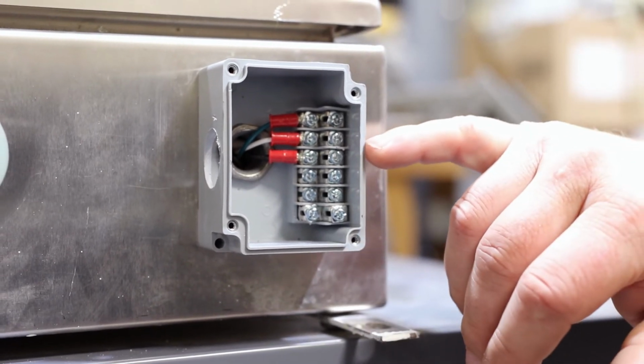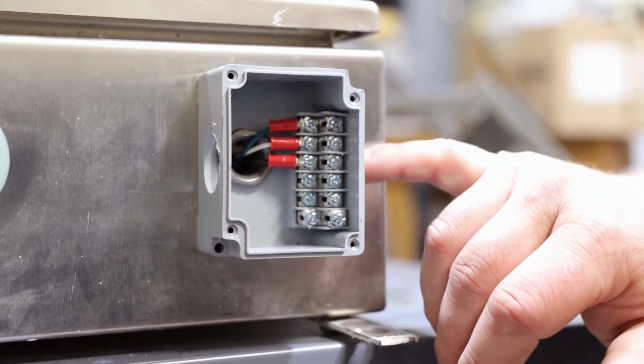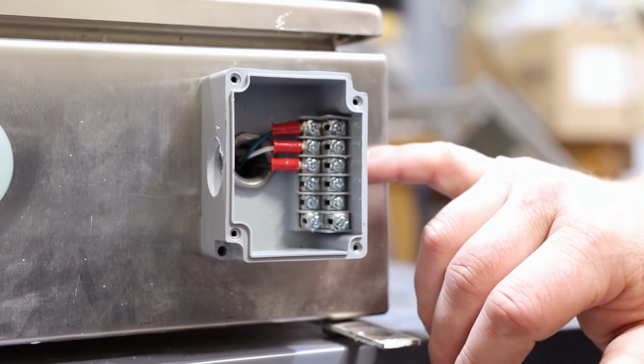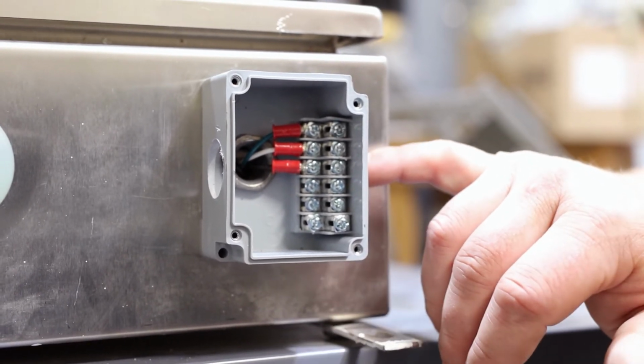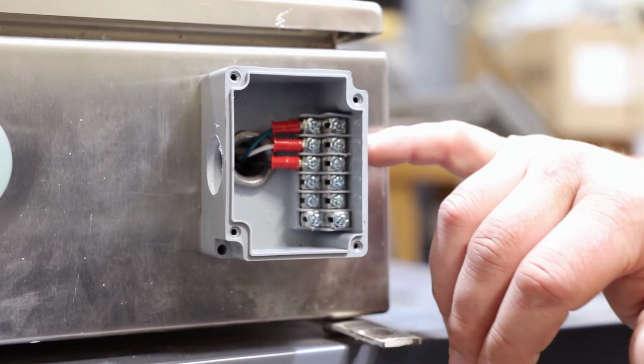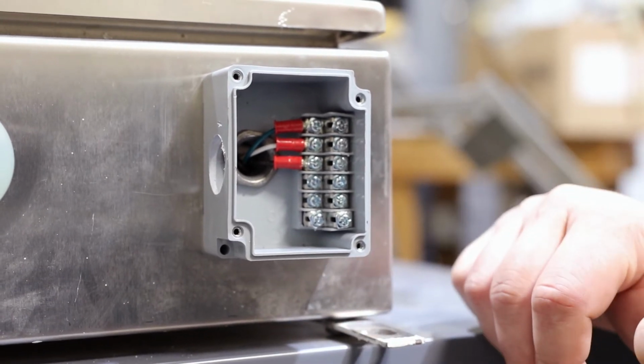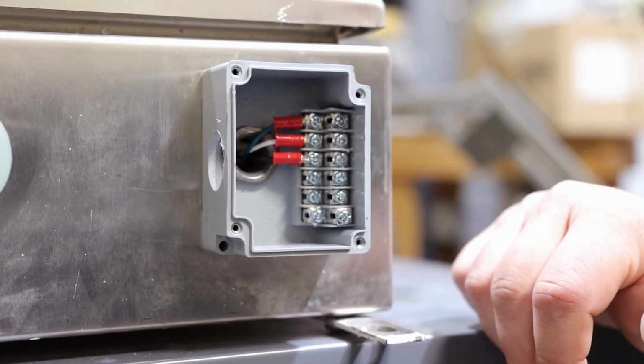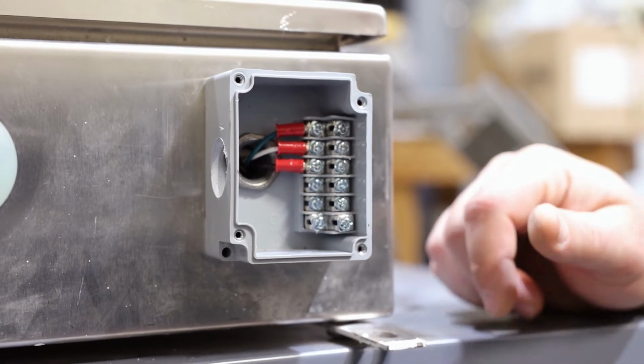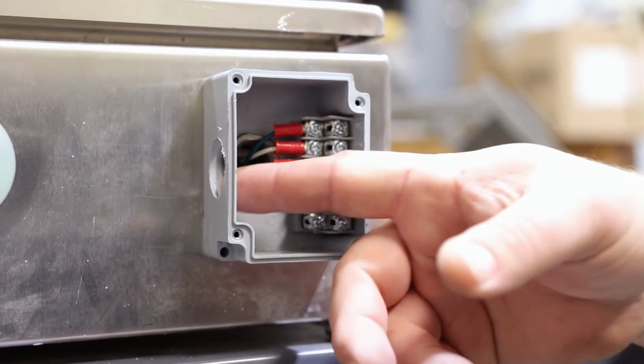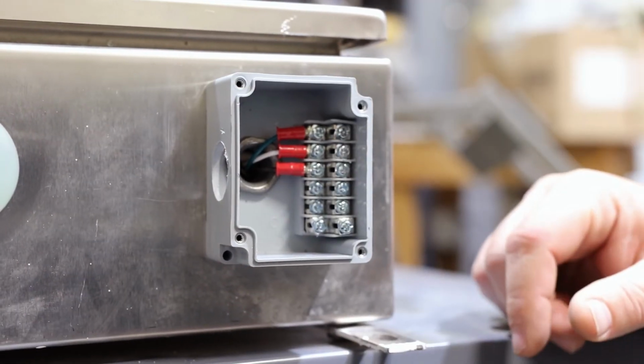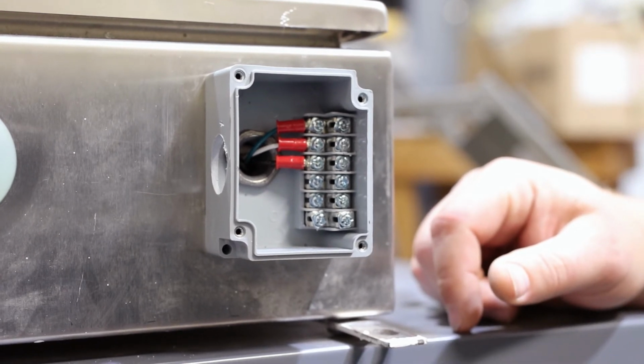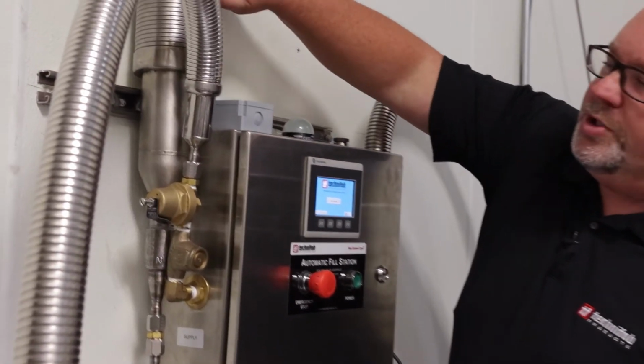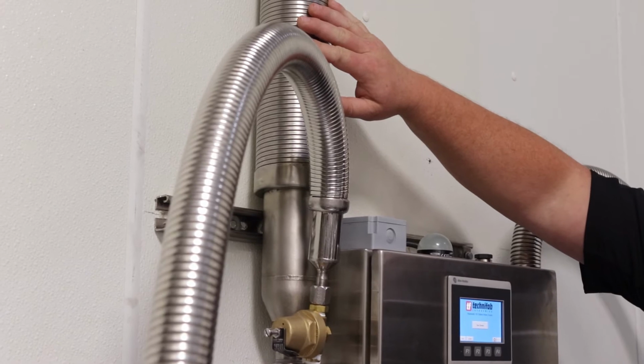You'll see there's a terminal above each one that the appropriate wire needs to be landed. So your black wire's on the third one, your white wire's on the second one, your ground or green wire is on the top one. Connect those up correspondingly. There's a knockout on either side for you to route to wherever you want to hardwire this in.